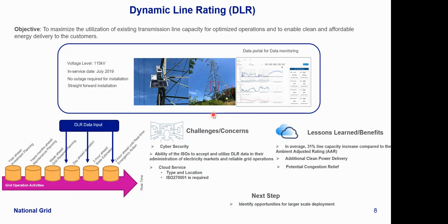So how do we make sure we can use existing capacity of our transmission lines without just relying on static ratings, while still keeping our system safe and reliable? One solution is called dynamic line ratings, where it looks at temperature, wind speed, icing, sag of the transmission line, and considers all of these, using the IEEE equation to calculate the rating of that transmission line.